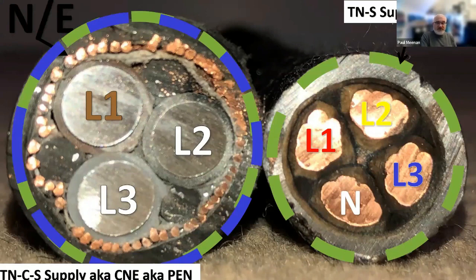And that's called a concentric. So what they did was they went with 3 phases aluminium, and they then went with a copper armoring or sheath, and that's the neutral and earth combined. Henceforth, in that photo, they split the neutral and earth. Now, the problem with that is with the combined neutral and earth, if you lose it, then you potentially have diverted neutrals, you potentially have a rise in voltage.